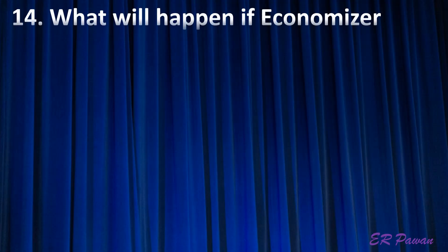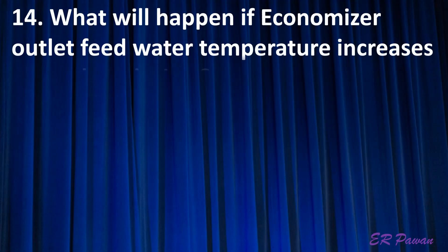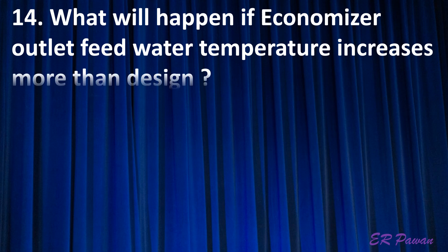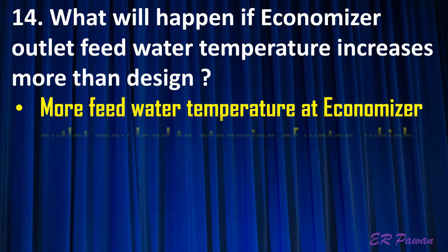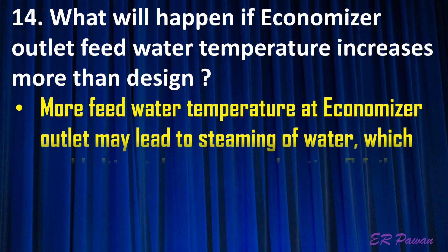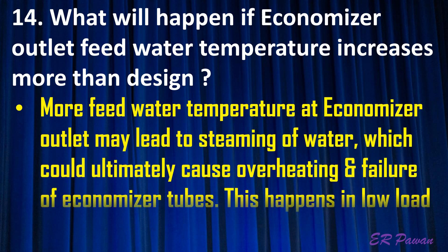Question 14: What will happen if economizer outlet feed water temperature increases more than design? More feed water temperature at the economizer outlet may lead to steaming of water, which could ultimately cause overheating and failure of economizer tubes. This happens in low load operation.